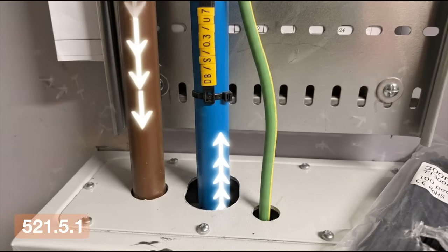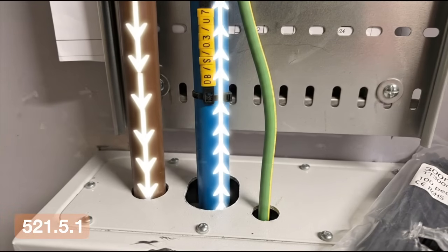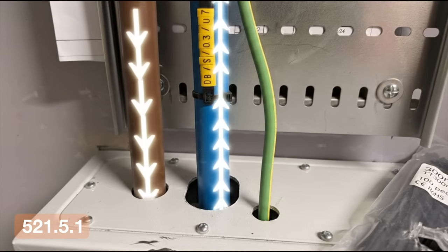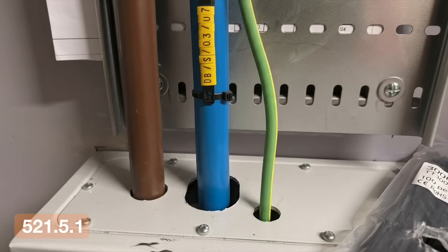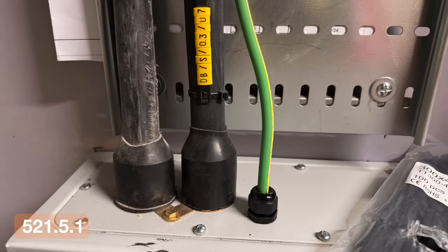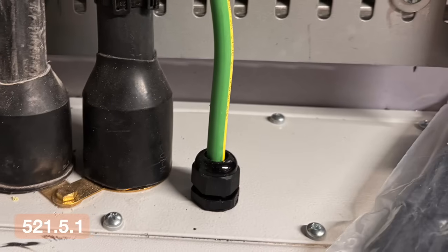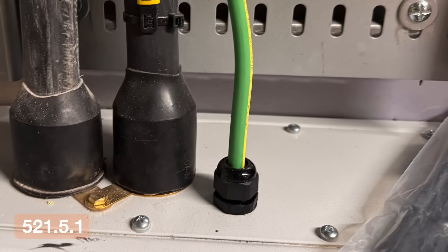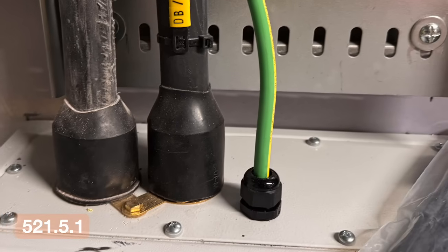Regulation 521.5.1 has also been clarified around electromagnetic effects in ferromagnetic enclosures. In simple terms, if conductors carrying current are split across different entries into a metal enclosure, they can induce current into that enclosure. That can lead to heating and unwanted electromagnetic effects. So the clarification now makes it clear that all conductors of the same circuit should pass through the same opening. There are exceptions. A CPC can be run separately, and armoured cables or correctly terminated glands can manage this through their construction. But the principle is that the magnetic fields cancel out when the conductors are kept together.